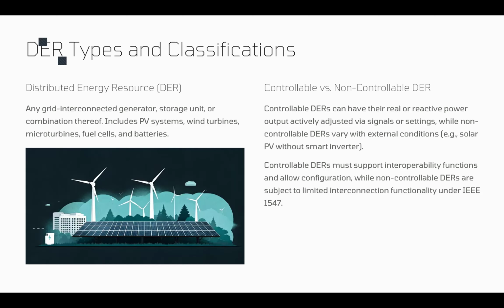It could be smart inverters, battery energy storage systems, or microturbines with remote dispatch capabilities. So basically, those controllable DERs should support the advanced functions defined in the IEEE 1547, like the volt-var that we mentioned, or volt-watt, or frequency-watt control. So these controllable DERs are the ones that we can use as a tool, as leverage, to address the challenges and apply those requirements at the point of common coupling.